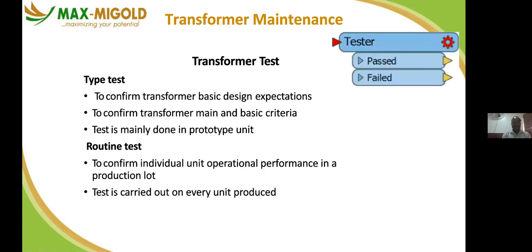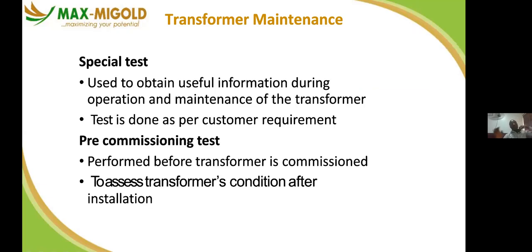So we have transformer tests. Why do you test? To confirm transformer basic design expectation, to confirm transformer main and basic criteria. Type test is mainly done on a prototype unit. So you have routine tests to confirm individual unit operational performance in a production lot. So a test is carried out on every unit produced. All the components that make up the transformer must be tested for them to deliver what is expected. We have special tests. For this, you engage a professional who knows how to do this test on a regular basis. So you don't just call anybody to come and test or work on your transformer. At the end of the day, they damage it. So they are carried out by specialists.